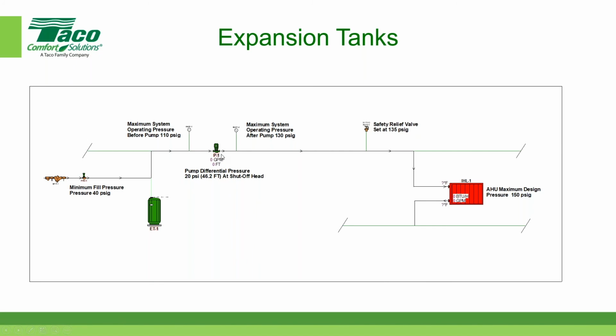The pump could be a variable speed pump, so the discharge pressure would be a function of the pressure differential across the pump. Well, if the pump is running at a very slow speed, the pump differential pressure, let's say, is just 3 pounds. I'll make up a number here. If the fill pressure is 40 pounds, the discharge will be 43 pounds. Remember that the point of no pressure change is at the pump suction. Now, as the pump increases in speed, the pump suction pressure remains constant and the discharge pressure increases as a function of the pressure differential across the pump.